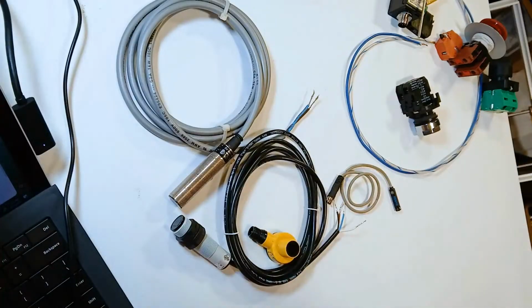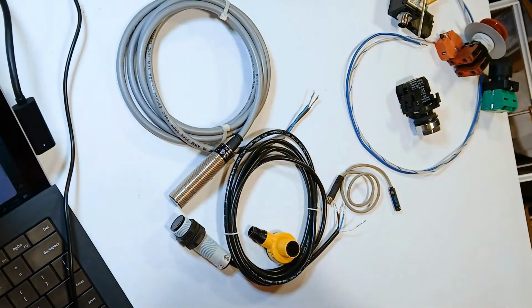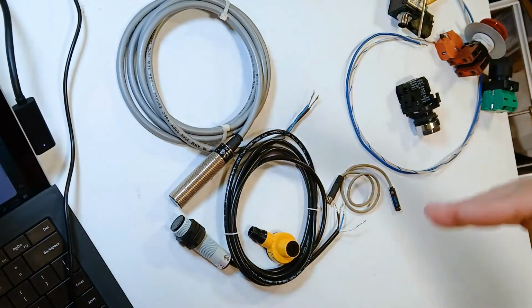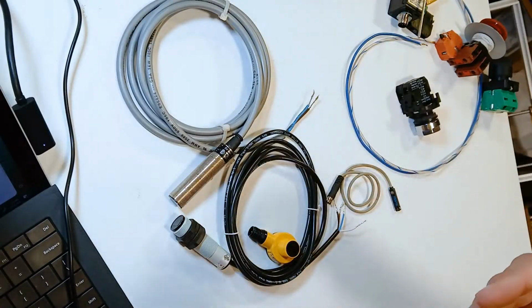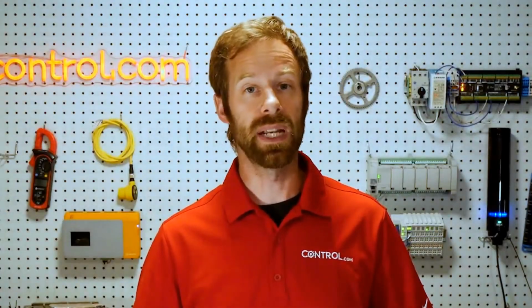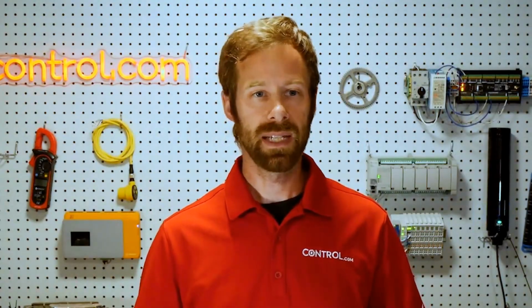But for the most part, most electromechanical sensors do not have any sort of indication to tell what state they're in. So when we are diagnosing a faulty sensor, how are we supposed to know if it's working or if it's not? With these semiconductor or three-wire sensors, very often an LED will show us whether it's currently sensing or not sensing, or whether it's outside of an acceptable range and sending back an error, and it can immediately pinpoint a problem. Much faster for troubleshooting, and even a few minutes of saved downtime can easily pay for the sensor.